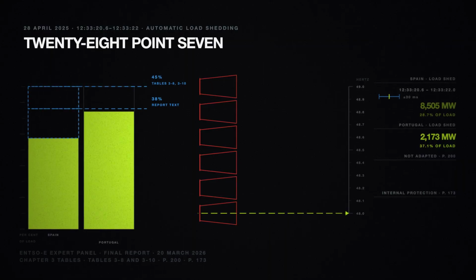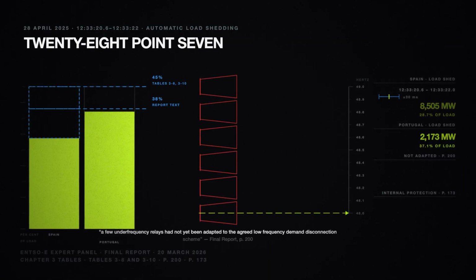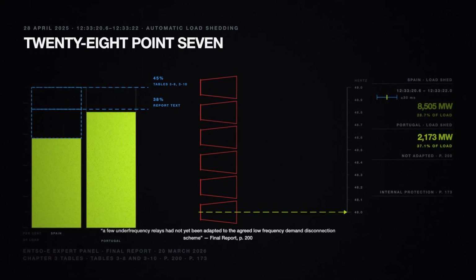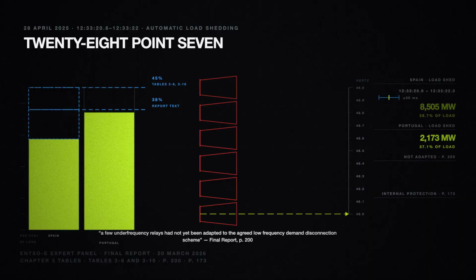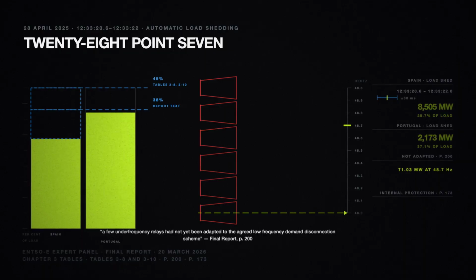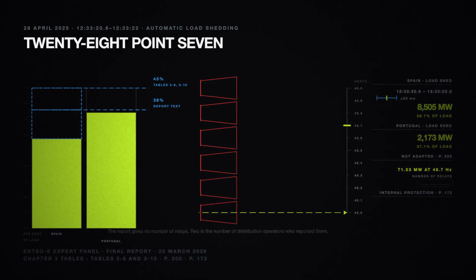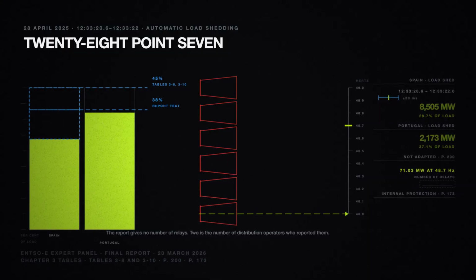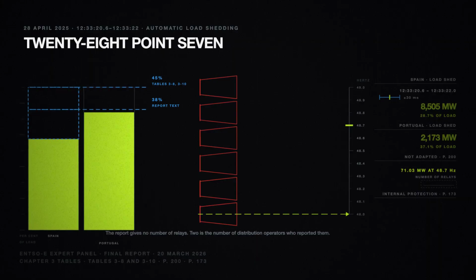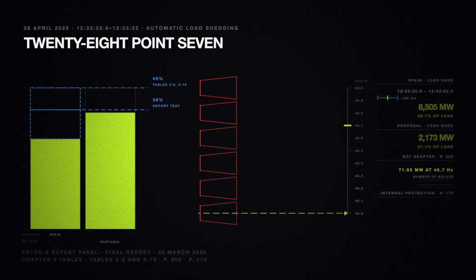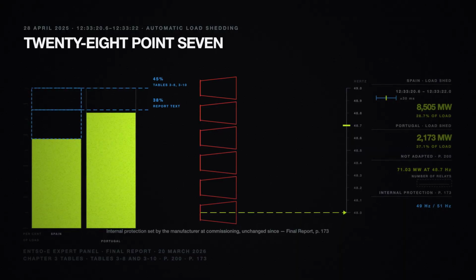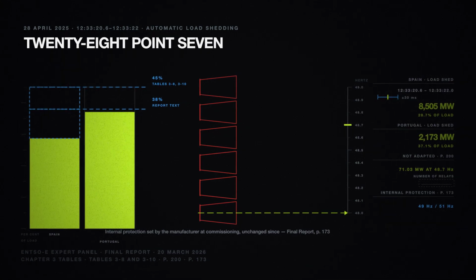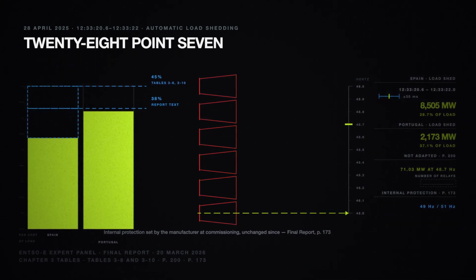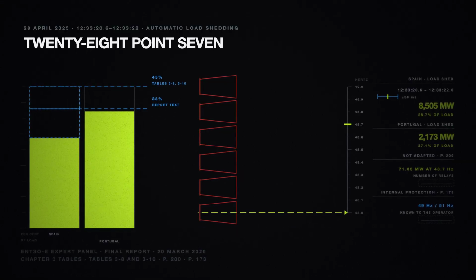Then a detail on page 200. 2 distribution operators reported that a few under-frequency relays had not yet been adapted to the agreed low-frequency demand disconnection scheme. As a result, 71.03 megawatts were disconnected at 48.7 Hz. How many relays that is, the report does not say. 2 is the number of distribution operators who reported it, not the number of relays. And in Portugal, some plants carry internal protection set at 49 and 51 Hz, set by the manufacturer at commissioning, unchanged since. The distribution operator did not know they were there.